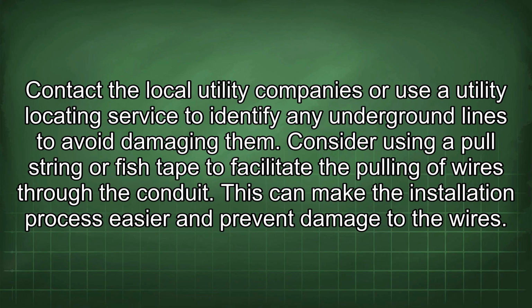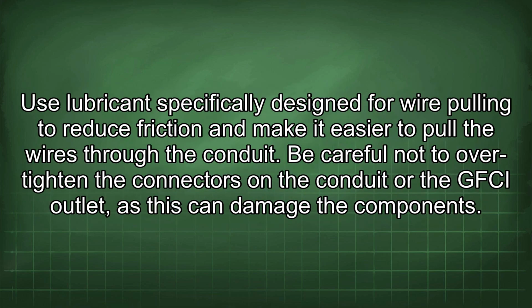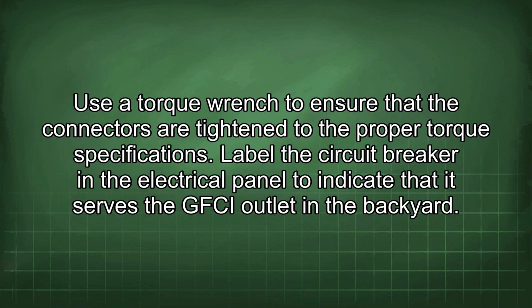Consider using a pull string or fish tape to facilitate the pulling of wires through the conduit. This can make the installation process easier and prevent damage to the wires. Use lubricants specifically designed for wire pulling to reduce friction and make it easier to pull the wires through the conduit. Be careful not to over-tighten the connectors and the conduit or the GFCI outlet, as this can damage the components. Use a torque wrench to ensure that the connectors are tightened to the proper torque specifications.